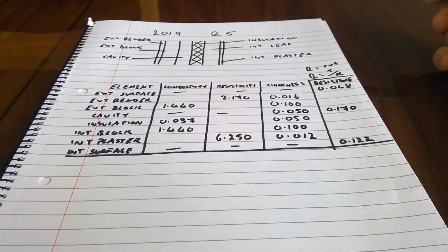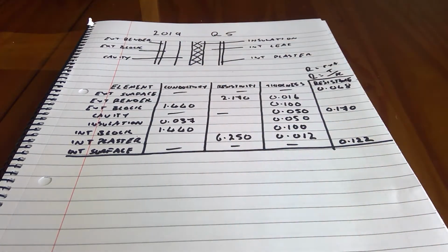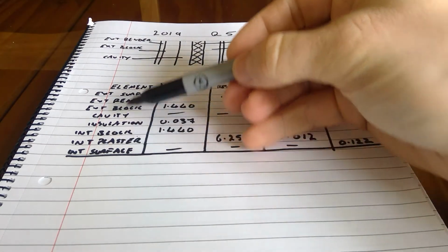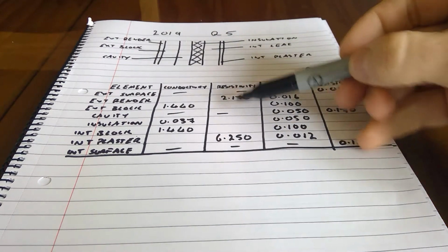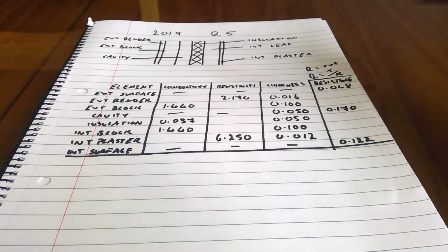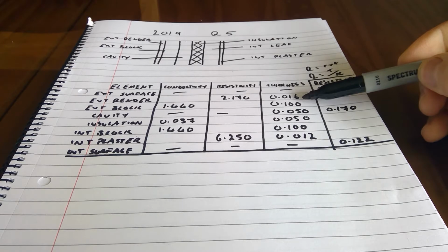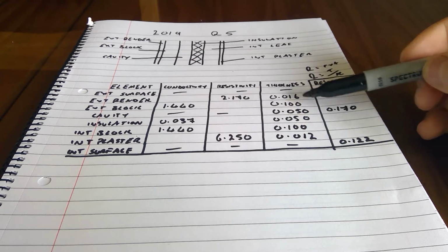Okay, at that point then you would draw up your table. This table here, just for the sake of time, I've drawn up already. All your layers are there. I've worked from the outside in. There's your invisible external surface, there's your invisible internal surface, and everything else is drawn in, working from there across to there. All of this information is what is given to us in the question. So it's just a matter of drawing up your table, which you need to know how to do yourself, and then inputting the information. As we know, the question is going to give the thicknesses. That's going to be given as 16mm, 100mm, 50mm, 50mm, 100mm, 12mm, and when you put those into meters, that's what they should look like.